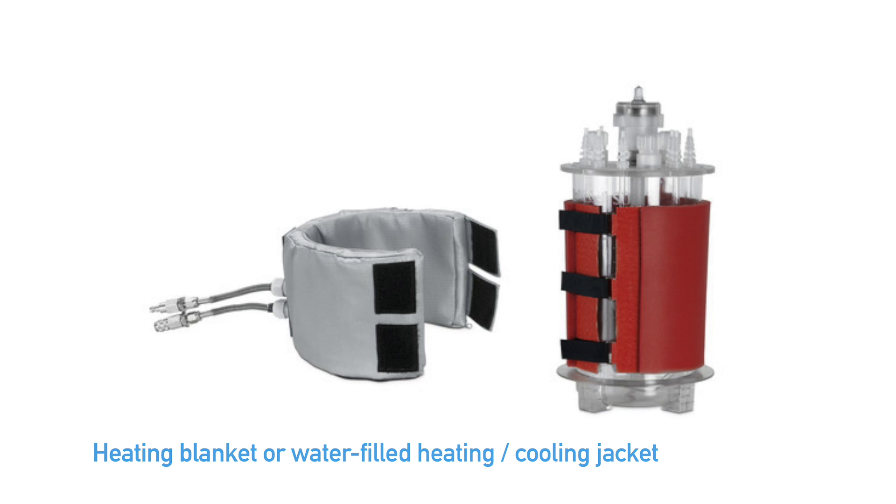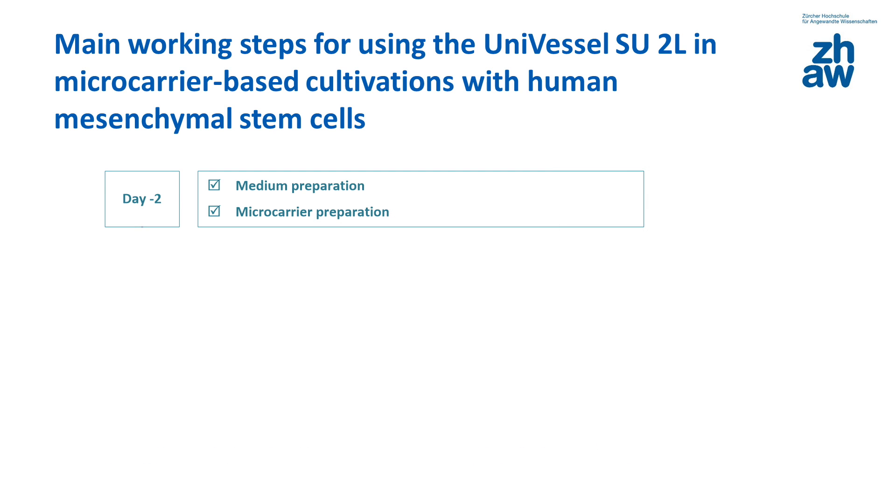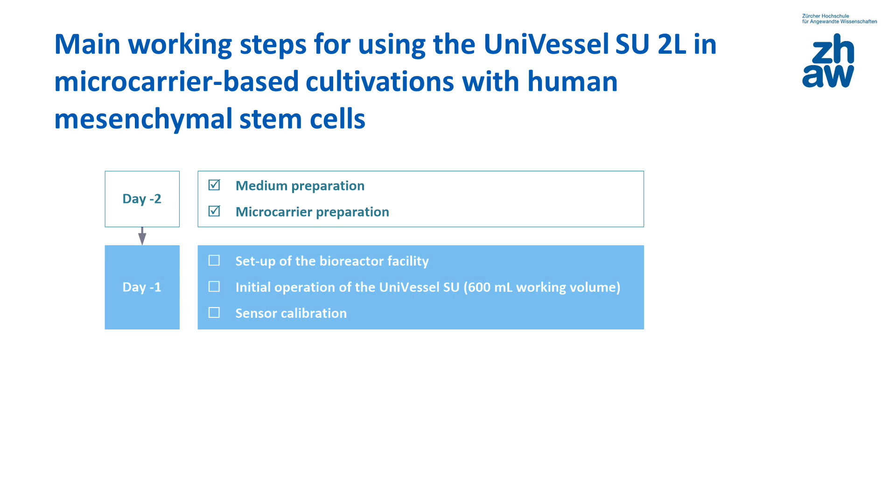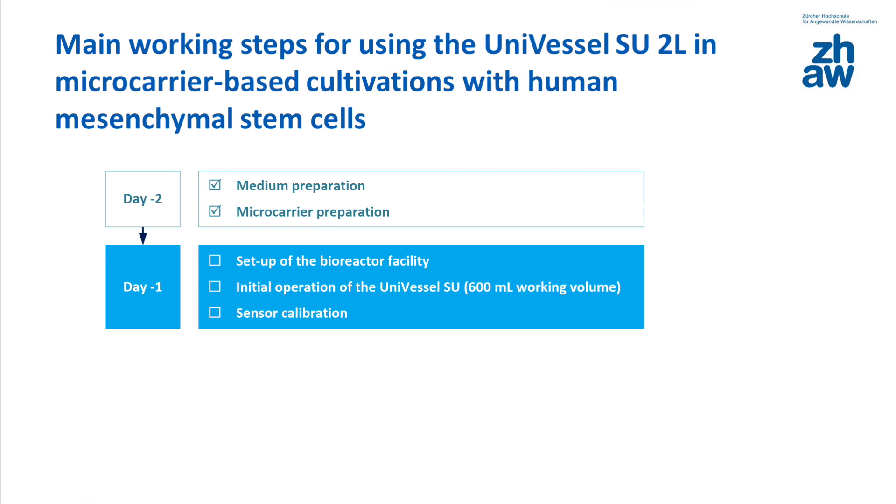With respect to temperature control, the vessel has a thermowell for the temperature sensor and either a heating blanket or a water-filled heating and cooling jacket. The microcarriers and medium need to be prepared before cultivation, as well as the Univessel SU. To ensure proper sensor function, it is recommended that bioreactor preparation is started the day before inoculation begins.